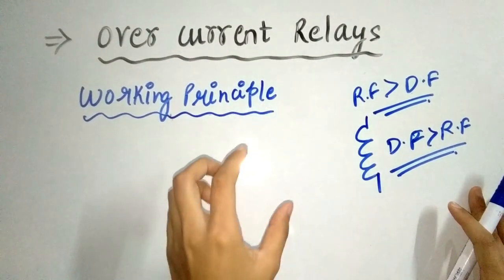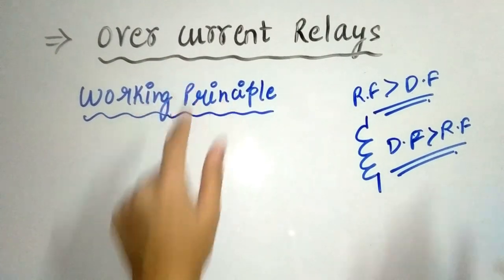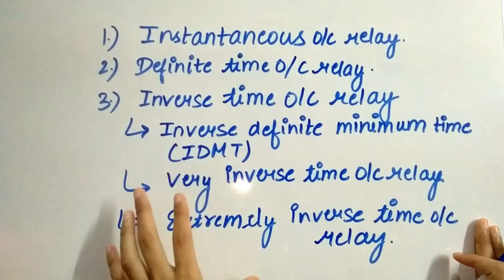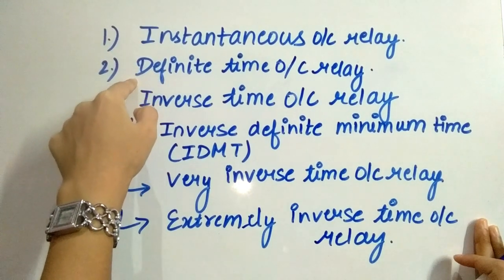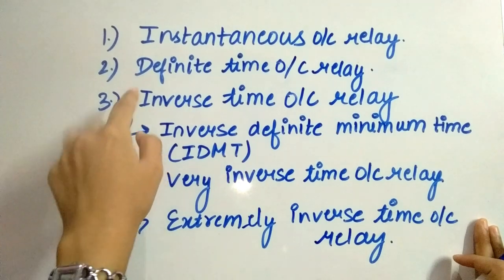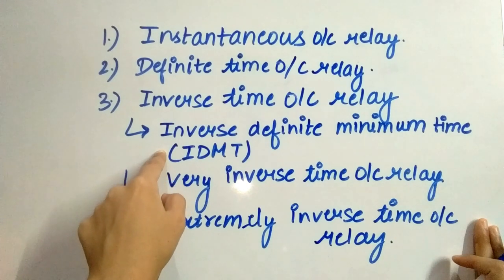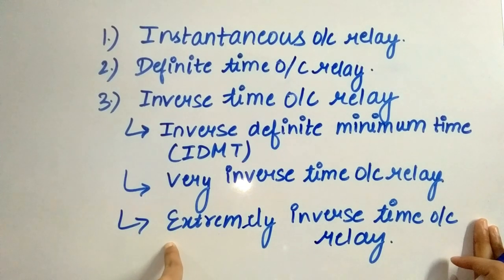The basic working principle is the same for all types of overcurrent relays. There are various types of overcurrent relay depending upon the time of operation: first is the instantaneous overcurrent relay, second is the definite time overcurrent relay, and third is the inverse time overcurrent relay, which is further subdivided into three categories — inverse definite minimum time (IDMT), very inverse time, and extremely inverse time overcurrent relay.